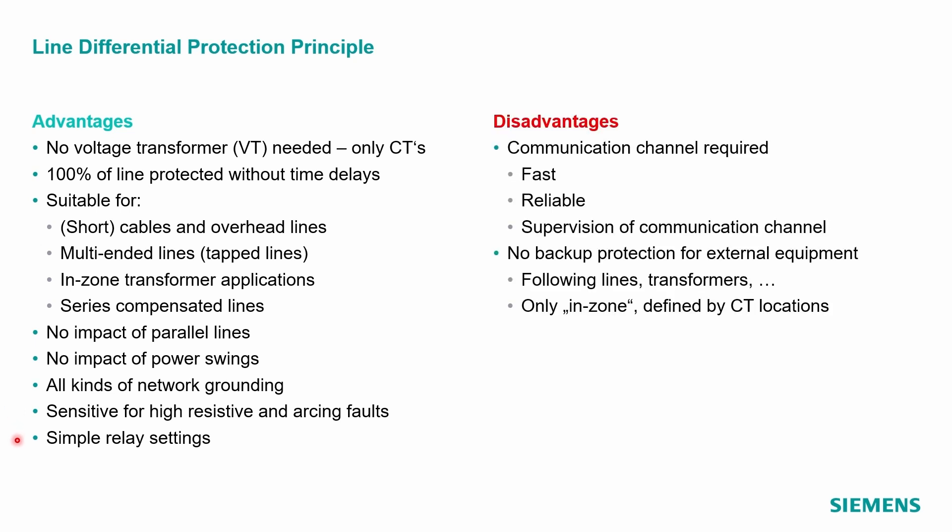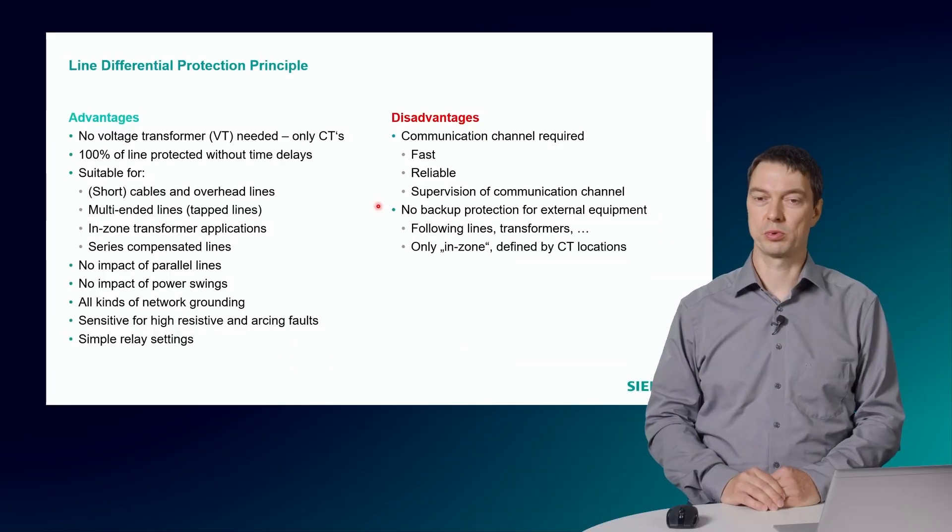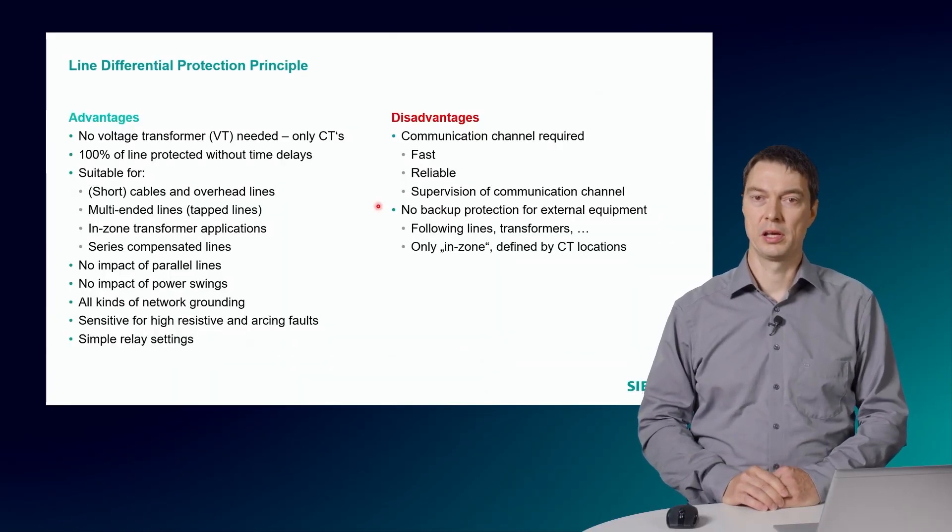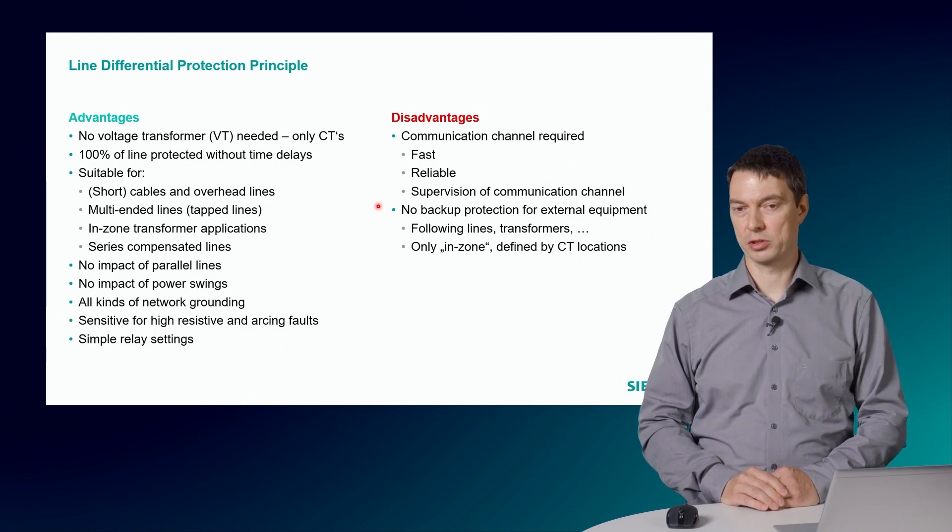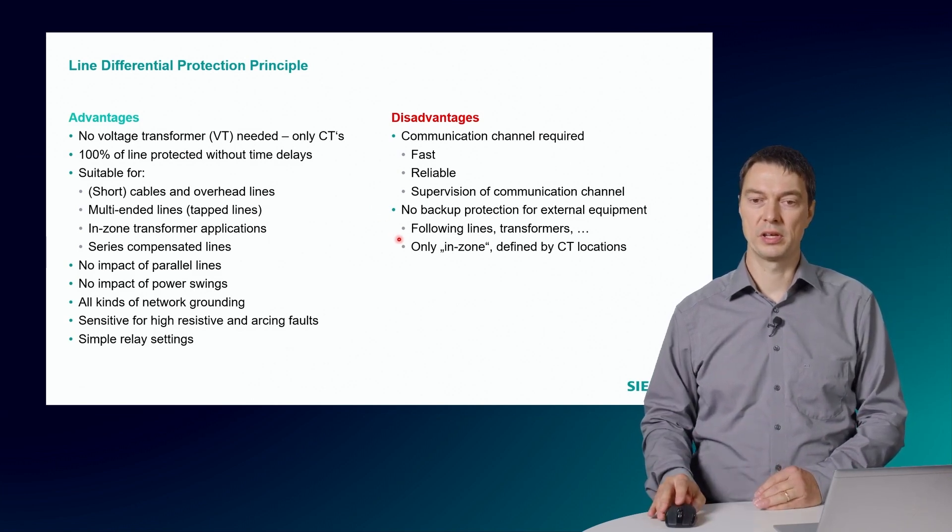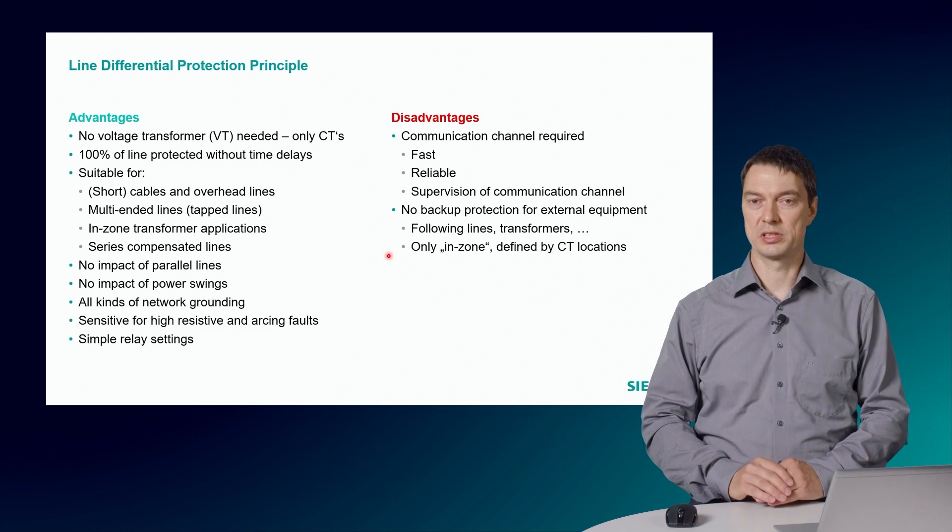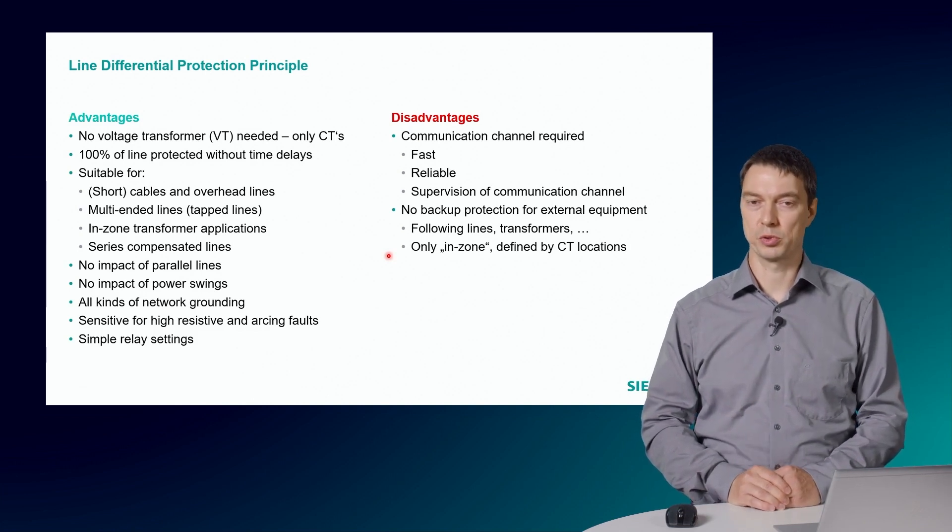On the other side, there are also some disadvantages to mention. First of all, you need a communication channel for this protection principle, which needs to be fast, reliable and it should be possible to supervise this communication channel. The Line Differential Protection is a unit protection. That means also that it does not provide a backup protection for external equipment like following lines or transformers. Only the equipment in the zone, which is delimited by the location of the current transformers, is protected.